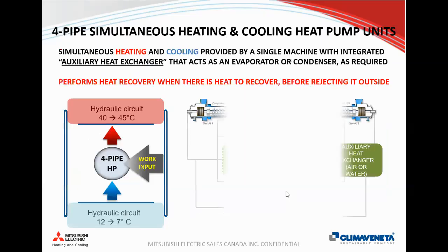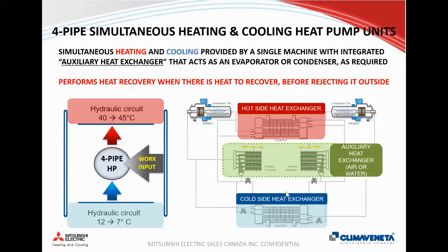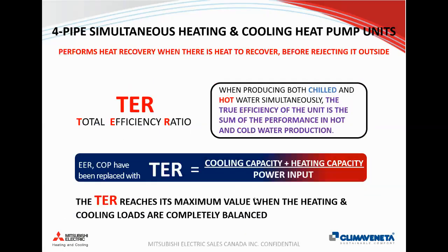heat. There's also a class of heat pumps called, this is just the diagram showing the different heat exchangers inside the units, but basically you can think of them as a machine that produces hot water and or chilled water as needed. And in these types of heat pumps, it's not necessarily a COP that we look at, but a TER, total efficiency ratio. And this is basically the cooling capacity plus the heating capacity divided by the power input.